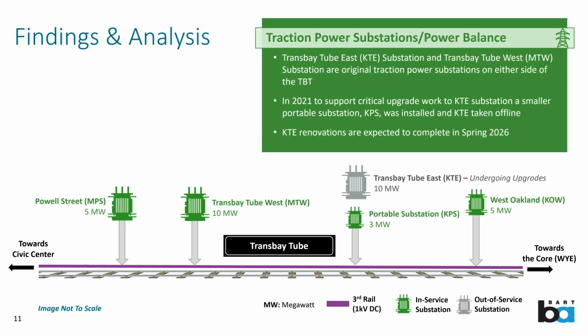Typically on the BART traction power system, substations are about 5 megawatts and roughly 1 to 2 miles apart. What's interesting here is that while we originally had 10 megawatts to the west and 10 megawatts to the east, that dropped to 3 megawatts. This is the only place on the system with a delta of 7 megawatts. This is being analyzed in terms of what's happening with the power flow - does it lead to an unbalance, is there a circulating current, for instance? These are some of the hypotheses that have been considered.